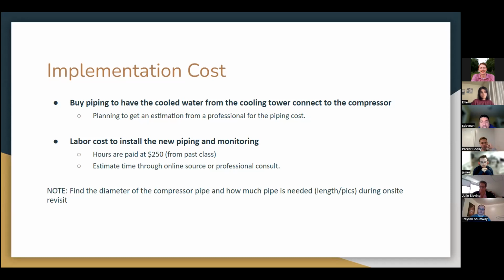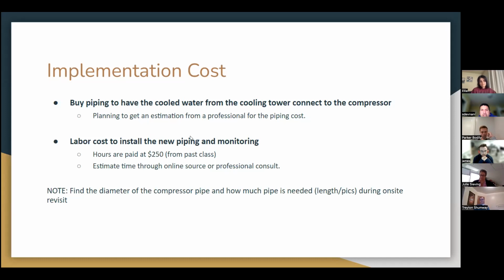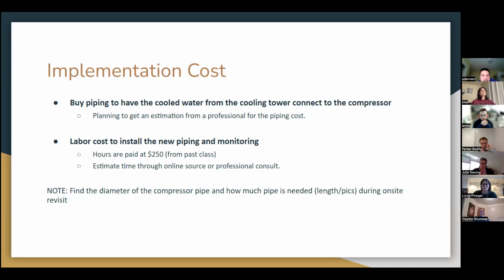Professional for piping costs. Yeah, I think you would be surprised with piping costs. Also, you might have, as you pointed out, diameter differences that start to really play games out there. You may also have to think about adding a pump, because you've got to move water through the cooling circuit of the compressor. So that's an increased head loss, right? More losses. So you may have to put a pump in there now on that loop.